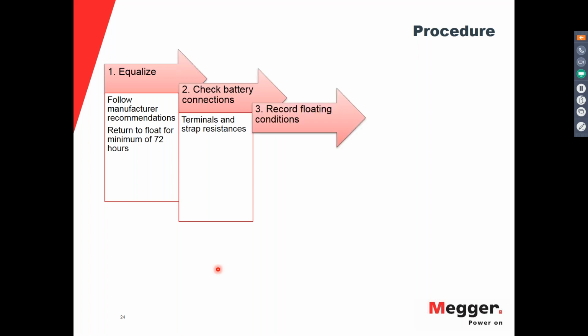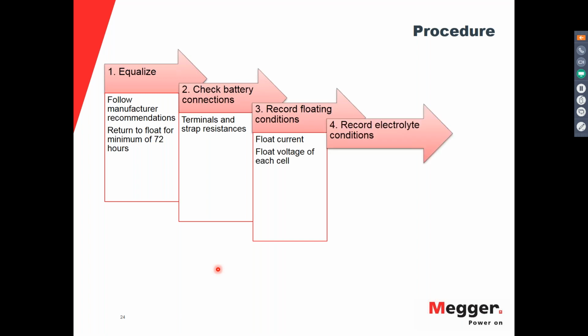Then you need to record all the floating conditions, float current and float voltage of each cell. You also need to record all the electrolyte conditions. This applies for VLA batteries, vented lead acid batteries, or vented batteries, because this could also apply to NiCad batteries. And this is the moment that you determine the temperature of your battery. Remember, this is a value that is important for the capacity correction factor. If this is a VLA battery, you should take that temperature from the negative post of the battery.